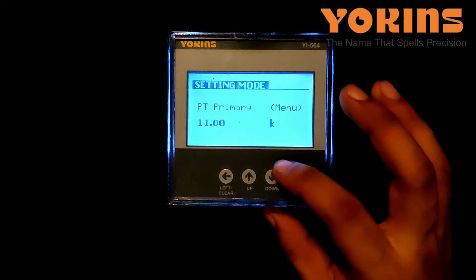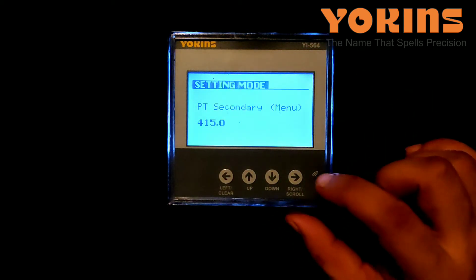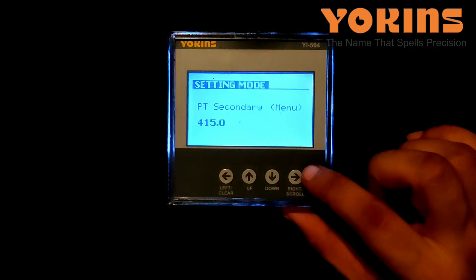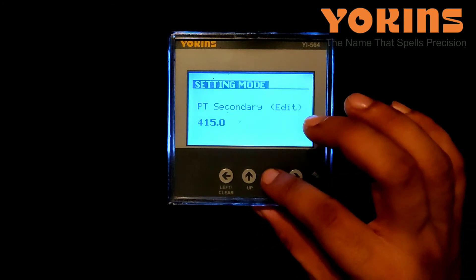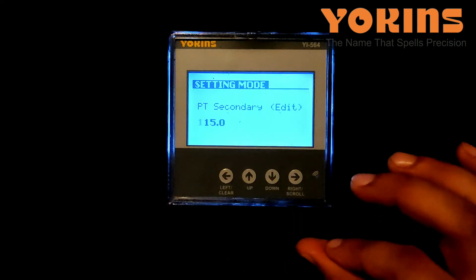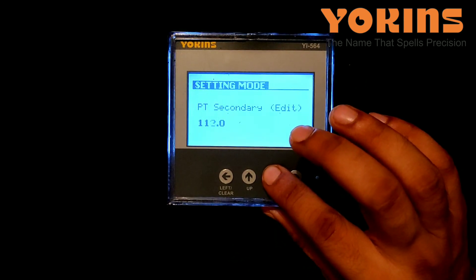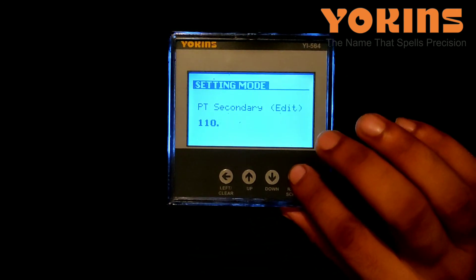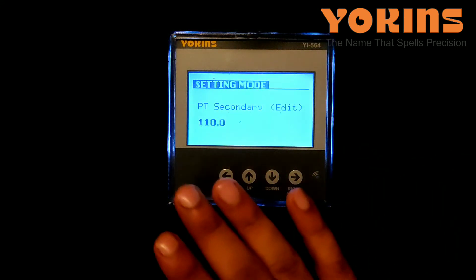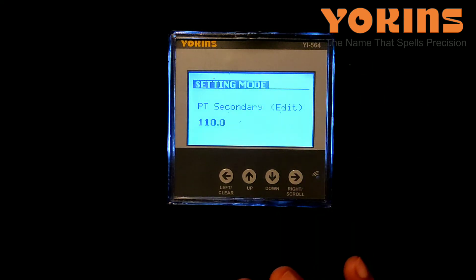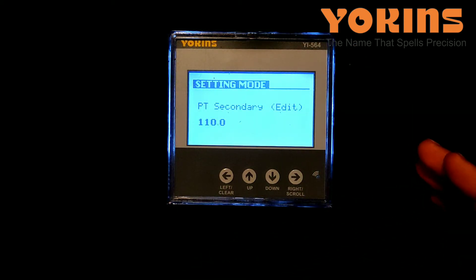Now we'll press the down button — PT secondary is shown here. We need to change it to 110V. Press right button; the display switches to edit mode with the first digit blinking. We'll press down to change it to 1, then press right button. The second digit needs no change. The third digit is blinking — we'll change it to 0, making it 110. We press right button again. Note that 'k' (kilo) should not appear here, as 110V is not in the kilo range.